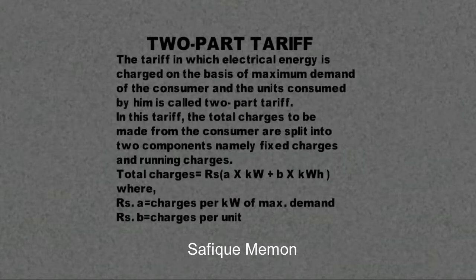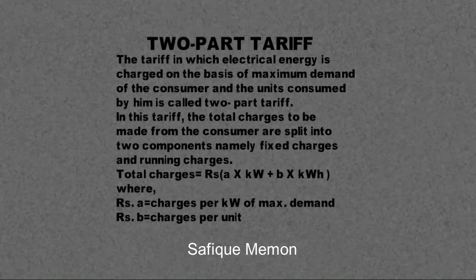Two-part tariff: The tariff in which electrical energy is charged on the basis of maximum demand of the consumer and the units consumed by him is called two-part tariff. In this tariff, the total charges to be made from the consumer are split into two components, namely fixed charges and running charges.